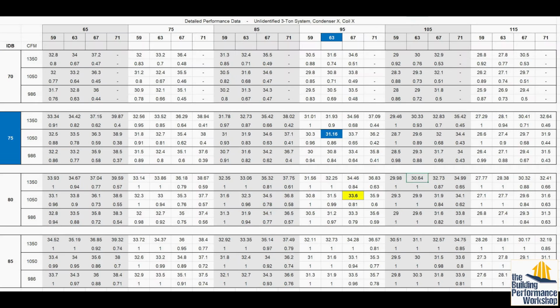Here's the thing. If I look up what the performance of this system is when it's 95 degrees outside, I'll give them that one. 75 degrees in the return and a 63 degree wet bulb. The performance of this system turns into 31,160 BTUs. Just a little over 2.5 tons. Just barely, right? We think of a 3-ton unit as being 36,000 BTUs. Take it out of the laboratory, introduce it to the real world, and all of a sudden it is way closer to 2.5 than it is to 3.